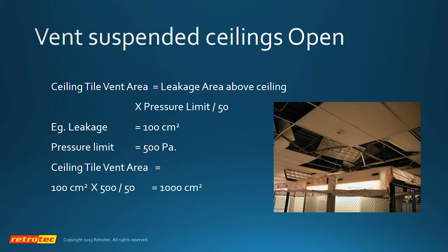in particular to clip the ceiling tiles down and hope that that will somehow take care of it. Those clips will be on there for a month, 6 months, whatever, maximum. Anytime someone accesses the above ceiling space, those clips will go flying. So I don't believe it's a good idea to rely on ceiling tile clips to hold them down. There has to be something better than that.